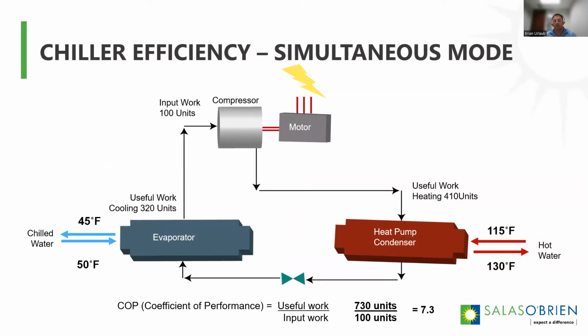So for instance, at these campuses, in the spring, summer, and fall, when you've got a high demand in domestic hot water every morning, but you're cooling the buildings, you're basically just making chilled water for the campus and then rejecting that heat straight to your domestic hot water and hot water loop. And so it effectively doubles your efficiency because you're doing two jobs with one lift, or one compressor, which no other system is able to do.